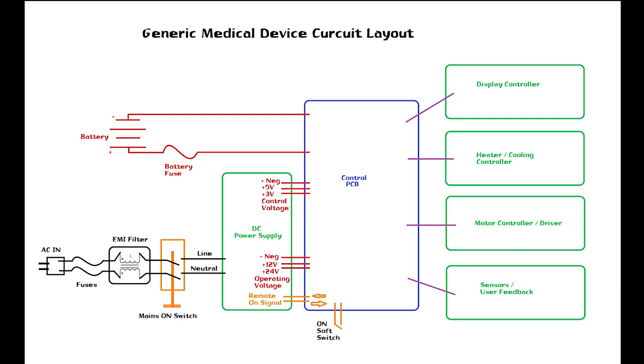And then from there, now you go in and you start checking fuses. One of the things you guys got to know though is if a device pops a fuse, there's a reason. This isn't the 1960s and 1970s anymore. If a device pops a fuse, I guarantee it's got bigger problems.